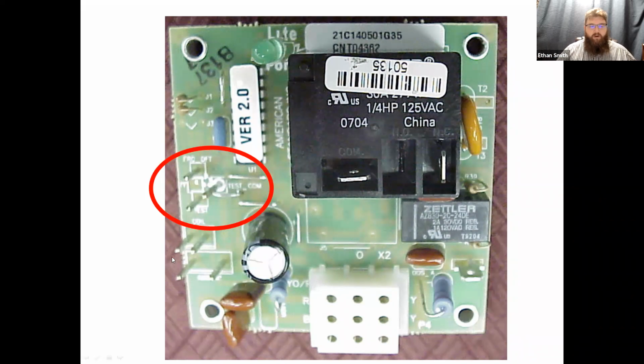Okay, but that coil sensor's right there. You can stick your probes right into the back of the plug and get a DC voltage reading, or you can unplug it and get a resistance reading to check your thermistor values. Okay, same thing there. We've got a coil and an ambient sensor right there.